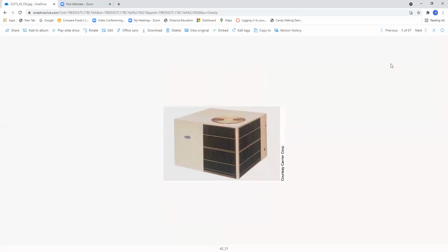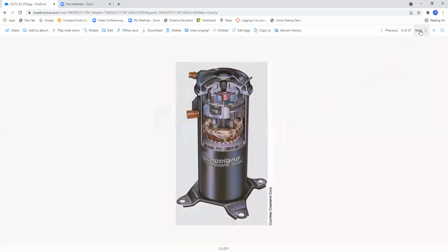Okay, here's a Carrier package heat pump system. And of course, all your components are located in here. You have your ductwork that connects up either side by side or bottom discharge on a roof curb. Scroll compressor, which is designed for heat pump application. They're beefier. They take a lot. They're designed specifically for heat pumps because of the high coefficient of performance factor that is involved.